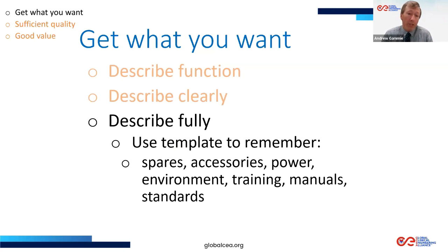Don't, as I said before, ask just for mains power, but ask for 230 volts, 50 hertz, or whatever is your local supply. For environment, don't just say robust. For instance, oxygen concentrators, you know, are very susceptible to humidity problems. And so you've got to say, if your environment is high humidity, your oxygen concentrator has to work above 80% or 90% humidity, whatever your local environment is. But be precise, describe it fully.